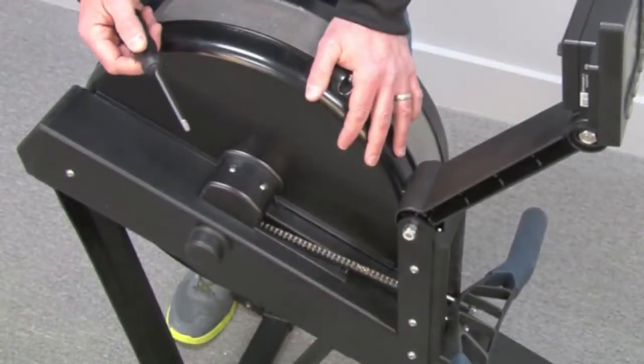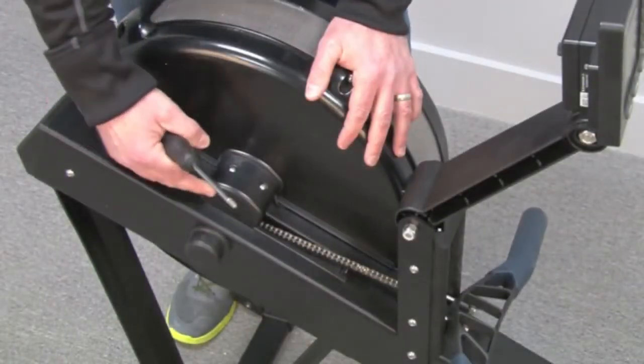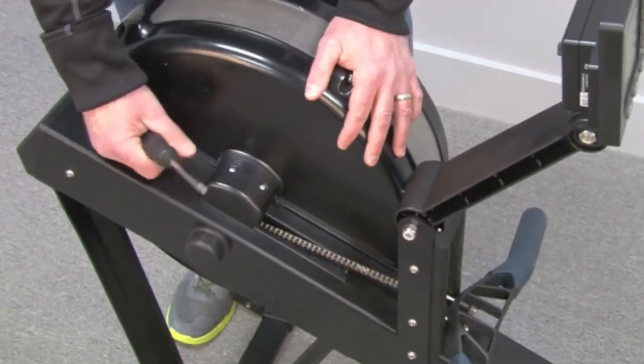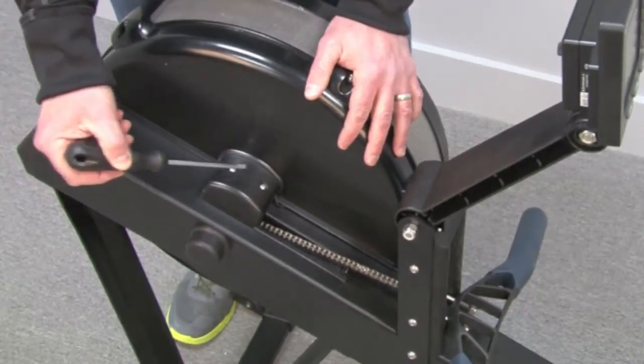The first step in replacing the generator coil is to remove the generator cover from the generator base. You'll do that by removing these two screws.